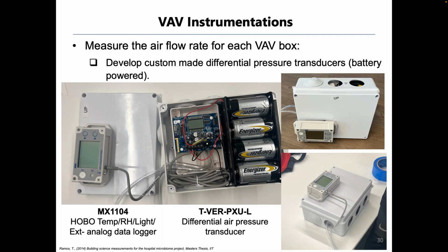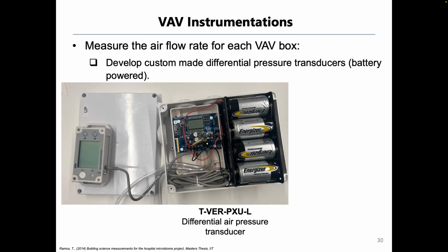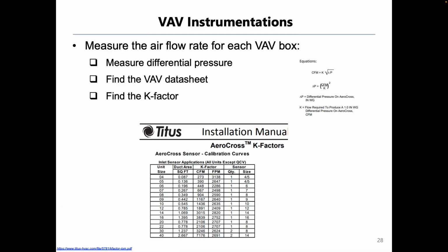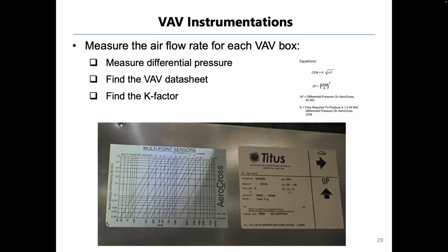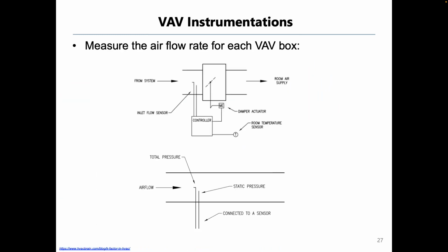Are there links to helpful formulas and information? You had shown those links, or actually shown the formulas. Is there a place where folks can go and get those? Yes, we can. In the presentation, if you look at the K factor, you could see some of the equations for this specific VAV box. Or if I go back here, this link at the bottom was super helpful to show VAV pressure-dependent and independent. But we are trying to wrap this up in a formalized journal publication, and we'll be happy to share it with the audience in a few months, and also come back and look at all the energy patterns. Okay, and that's something we'll be able to share as well when that happens. So we'll be happy to send that out to all the attendees as well.